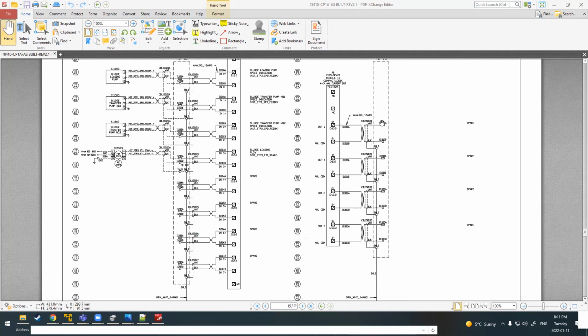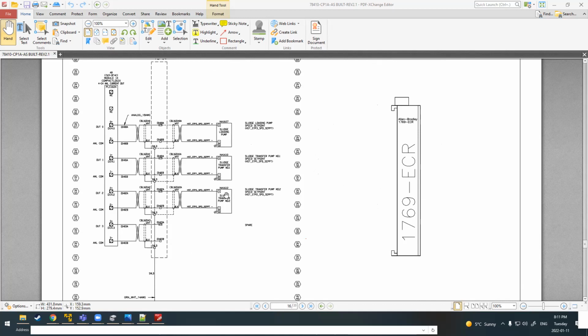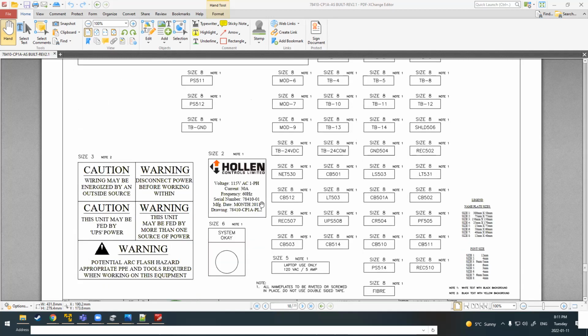Analog outputs are the same as the inputs. They're actually typically a lot easier because you know what the range is going to be. Most of the stuff that I've ever sent a signal to is 0 to 100% or whatever. It could be a specific type of pump that runs 0 to 20 liters per minute, and 20 milliamps is 20 liters per minute. Pretty straightforward, but the configuration is different for every device.